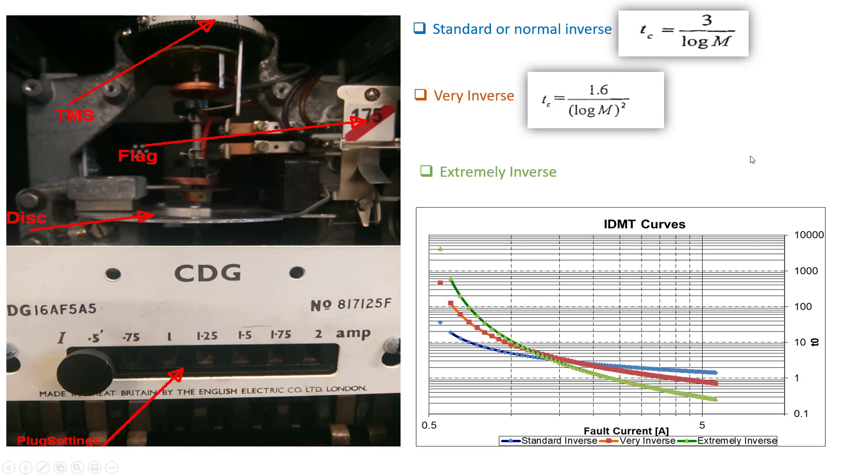Now the next one is the extremely inverse characteristics. The extremely inverse characteristics is also given with the same formula. But this time, the log M, which is M which stands for the multiple of setting current, is now raised to the cube instead of square on the very inverse. Now this characteristics is mostly used for relays that have to discriminate with fuses.